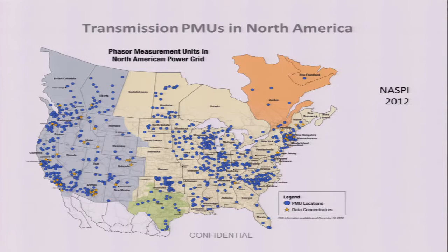Let me go back to this version of the timescale, which is to say that we're looking here at intervals down to less than a degree of angle. Now, the degree refers to the oscillation of voltage back and forth. So one complete cycle would be 360 degrees. 1 degree would be 1/360th of 1/60th of a second. That's about the resolution of your typical transmission phasor measurement units, or PMUs. At the distribution system, which is where we are going to look, you need a much better resolution because you're looking at shorter distances and smaller power flows, so the angles are going to be smaller. You need a more sensitive instrument.